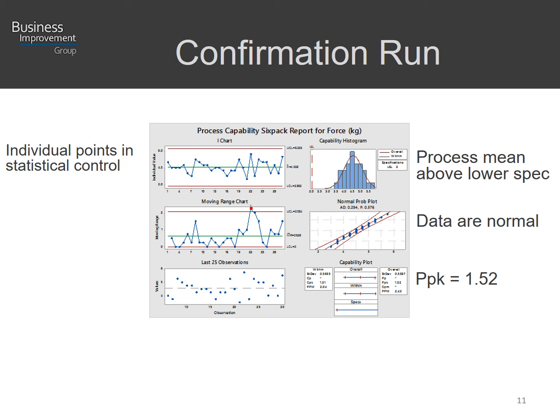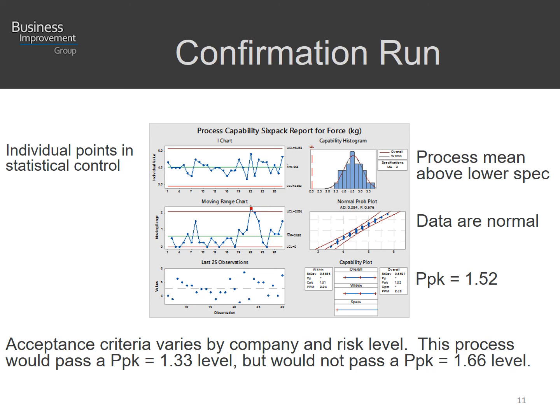We have a process performance index PPK of 1.52, which is a measure of how well a process can perform and produce a particular output. In the medical device industry, acceptance criteria can vary by company and are also based on risk, but common levels are 1.33 and 1.66. This particular process would certainly be acceptable at the 1.33 level, but would not pass at a PPK of 1.66.